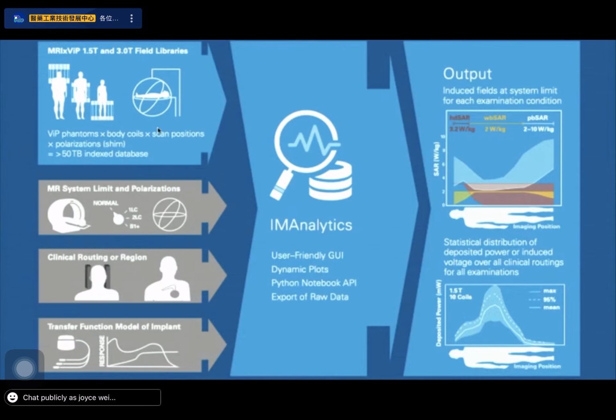But what you have to do is generate this for a whole range of data sets. So you need 12 anatomical models, 10 birdcages, head to foot scans, different polarizations, and you've got maybe more than one implant model. And you also have to consider the scaling of that. So are you running your MRI at normal mode? Are you running it at first level controlled mode? Are you running it at B1+ limitation instead of a SAR limit? Basically, this ends up being an enormous amount of data. And then this is a verified numerical tool, which just does all that math and gives you the statistics.